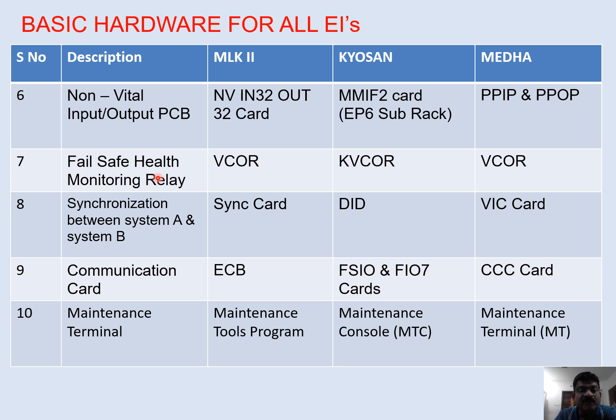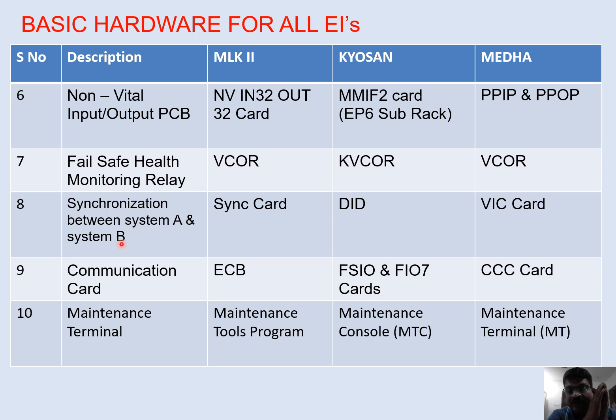The failsafe health monitoring relay — this is just like cross-protection in the normal signaling system, a cross-protection system for the whole system. This is the vital cut-off relay in MLK2, the Kyosun vital cut-off relay in Kyosun, and also called vital cut-off relay in MEDA. For synchronization between System A and System B: EI has redundancy with two systems working in parallel. In Microlog 2 a sync card is used for synchronization — both systems speak with each other regularly and share their information. In Kyosun it is called the DID card, and in MEDA it is called the VIC card.